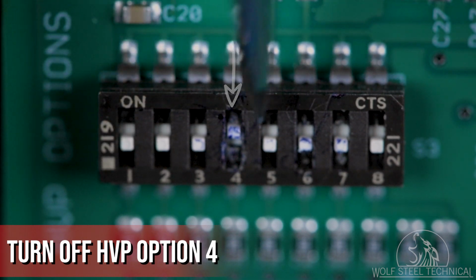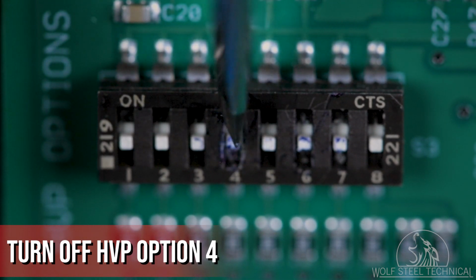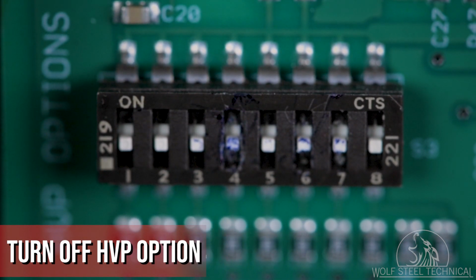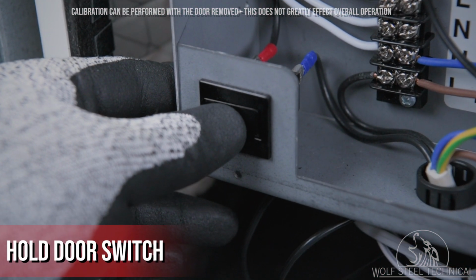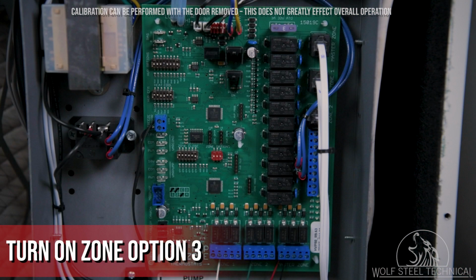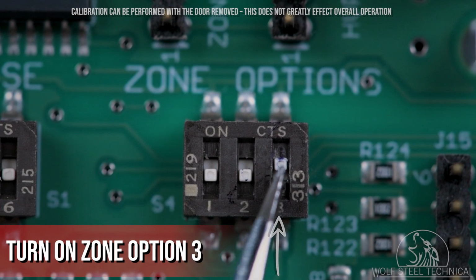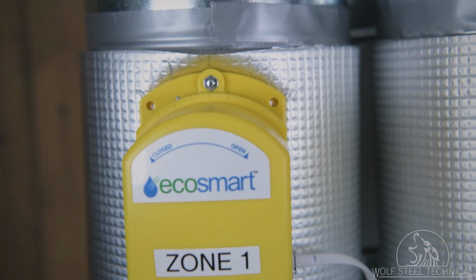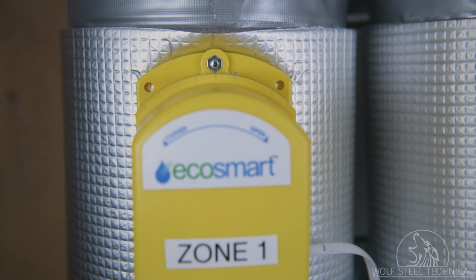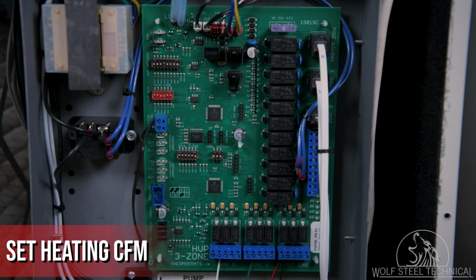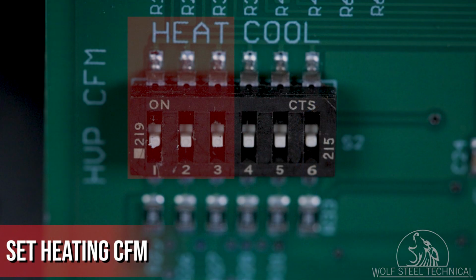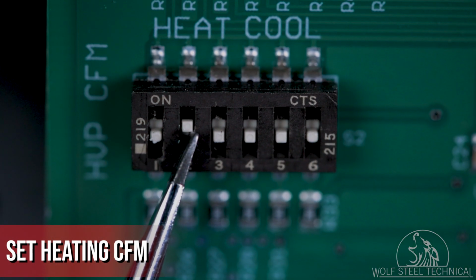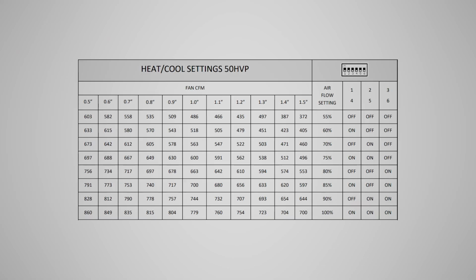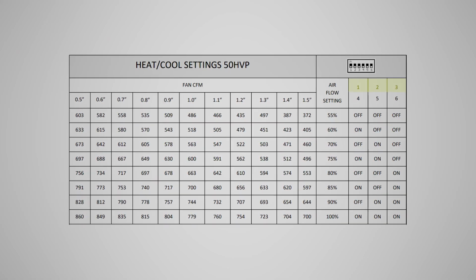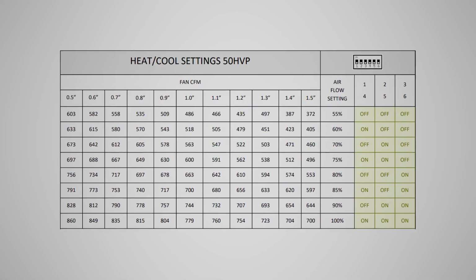Locate the HVP option 4 switch and ensure it is toggled to the off position. This is set as off from the factory. Now, hold the door switch in and locate and set the zone option 3 switch to the on position, which will force all the dampers open. Allow sufficient time for the dampers to fully open, then set the desired airflow rate using the heat CFM switches.